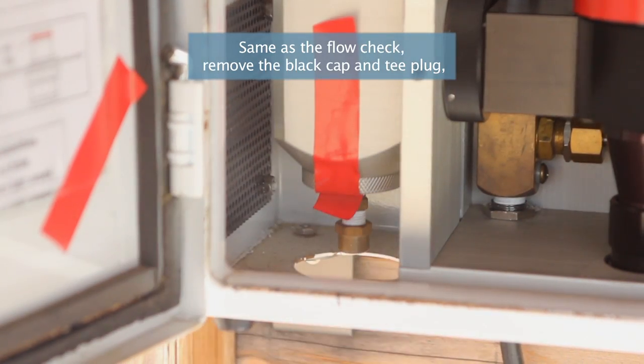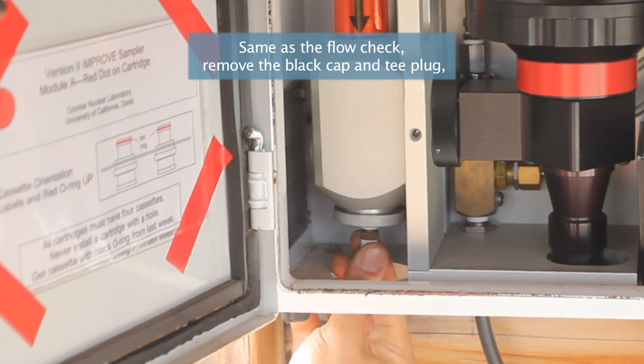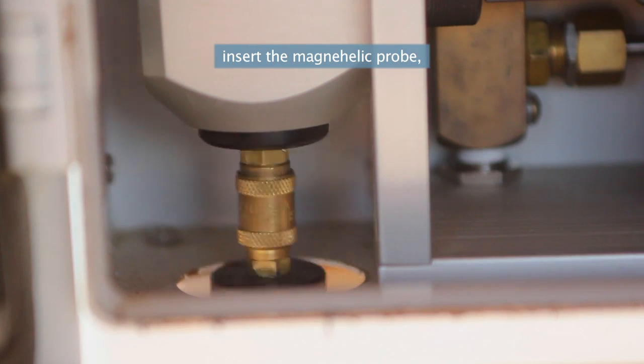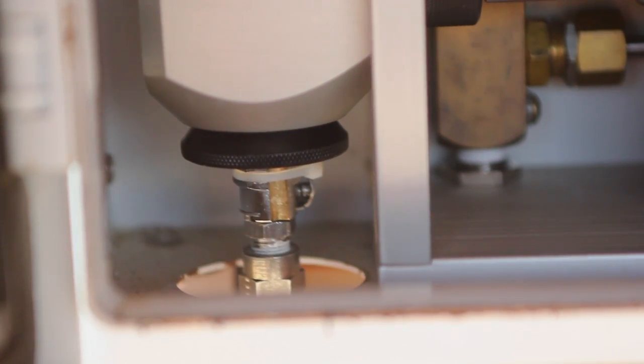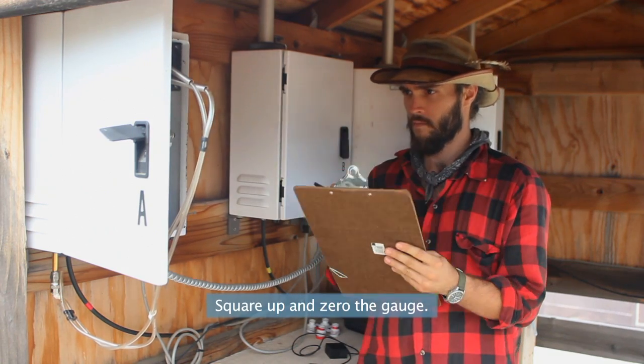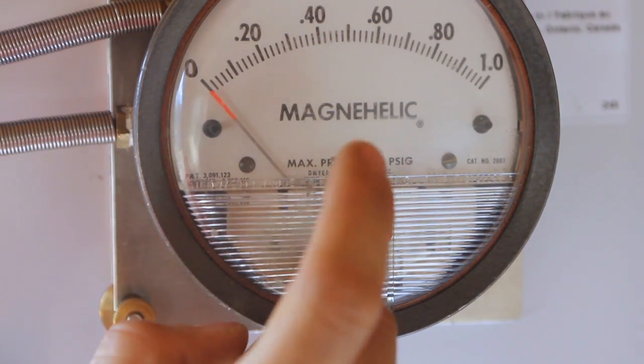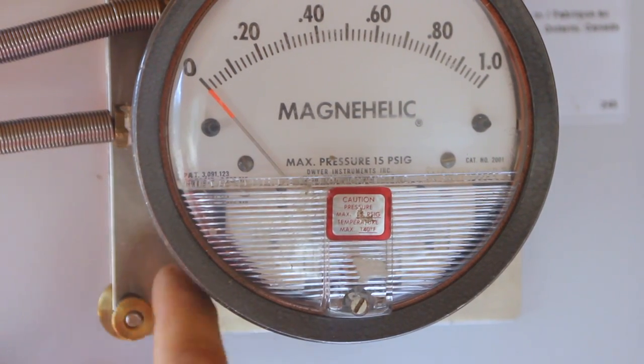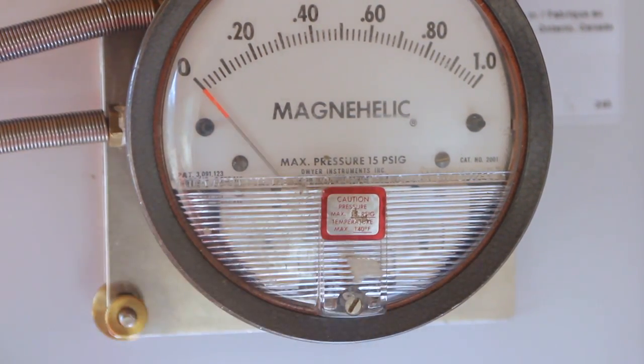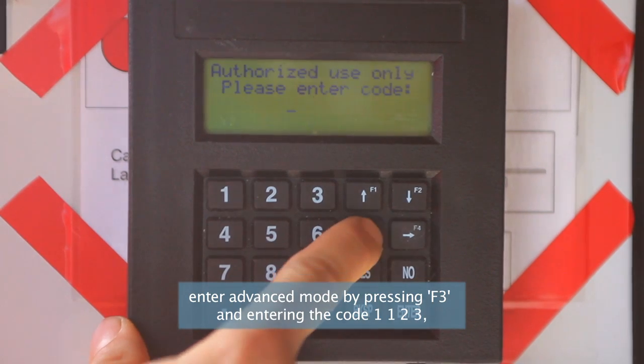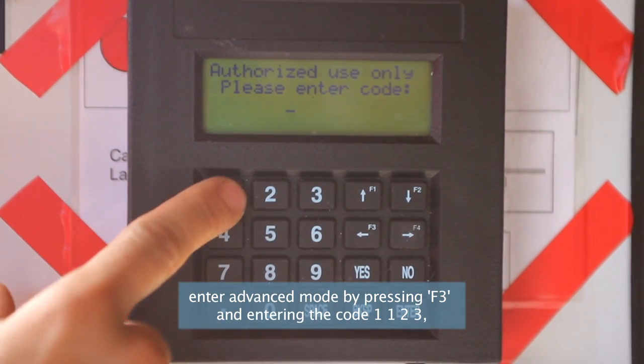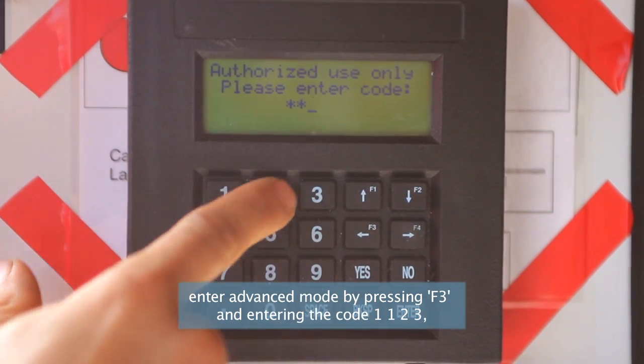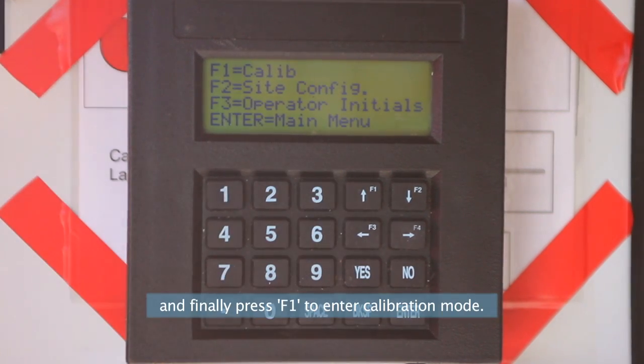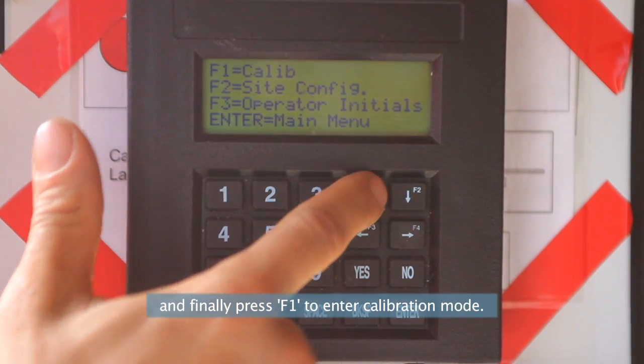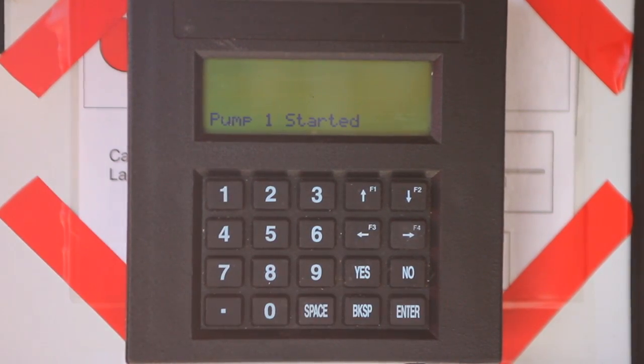Same as the flow check, remove the black cap and T-plug. Insert the magnehelic probe. Square up and zero the gauge. Enter advanced mode by pressing F3 and entering the code 1123. And finally, press F1 to enter calibration mode.